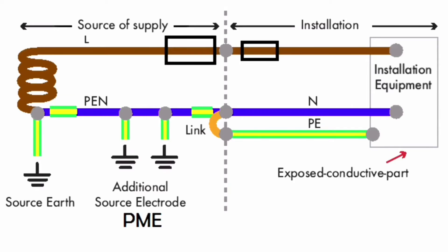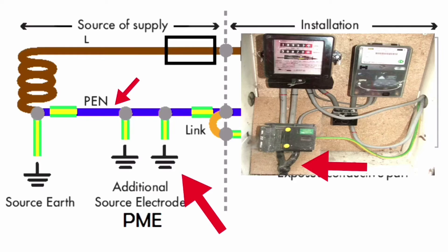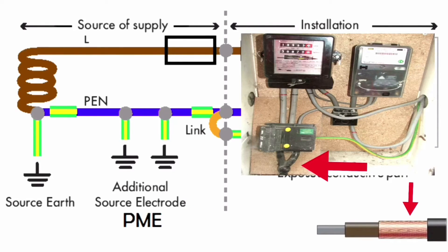The left-hand side of this drawing shows the Supply Authority's cable. It has a separate line conductor and a combined protective Earth Neutral conductor. This combined cable is the one we can see coming to the bottom of our cutout. This concentric cable has a copper Earth Neutral and an aluminium line conductor.